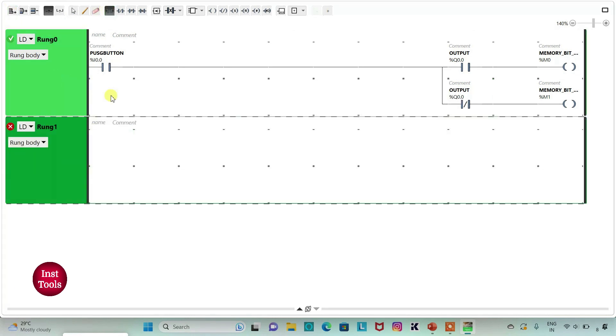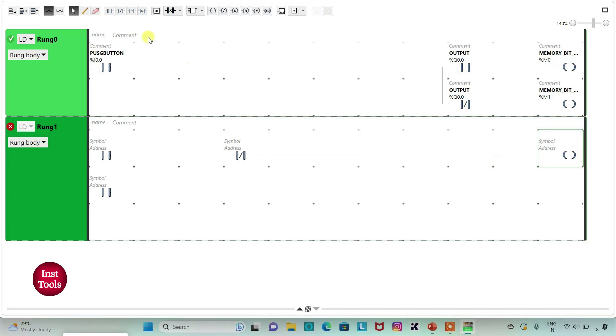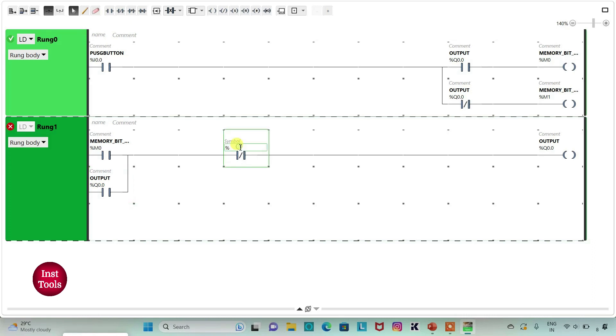And then I will insert normally open contacts and one normally closed contact and a coil. I will click on this option and draw a line like this. I will assign address to this contact as M0 — the memory bit which we will use to turn on the output, that is Q0.0. And then I will assign address to this normally closed contact as M1, the memory bit which will be used to turn off the output.